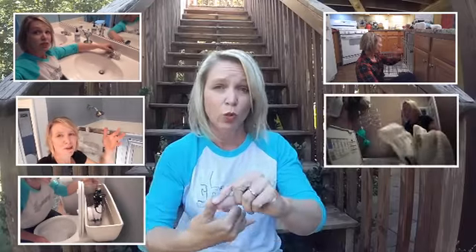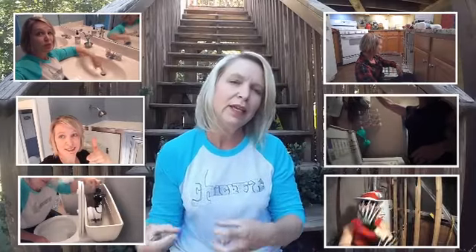Now, I have since learned that the immediate issue is more about the fixtures in your house than it is about your pipes. The sinks, the showers, the toilets, your dishwasher, your washing machine, your water heater. All of those things are designed to work with a certain amount of water pressure, and when it's too high, it's going to cause them damage and make them fail quicker. So you're going to have toilet valves that fail, or your water heater is going to go a lot quicker.